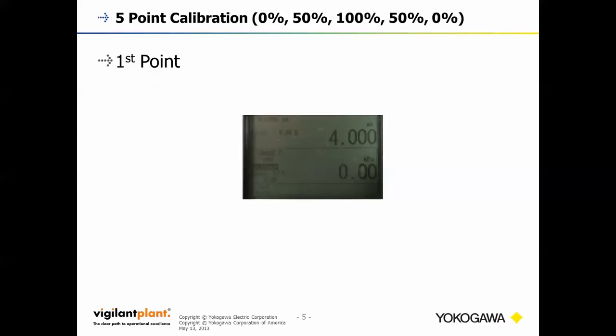So I've captured some screenshots of the first point that we did. You can see this is the analog output that we're reading from the transmitter, so exactly 4 milliamps. And at 0, both the transmitter and the calibrator are scaled 0 to 100 kilopascals. So this one's pretty much perfect. We've got 0 kilopascals reading on the calibrator, and then we've got a 4 milliamp reading on the analog output of the transmitter. So our error is 0.